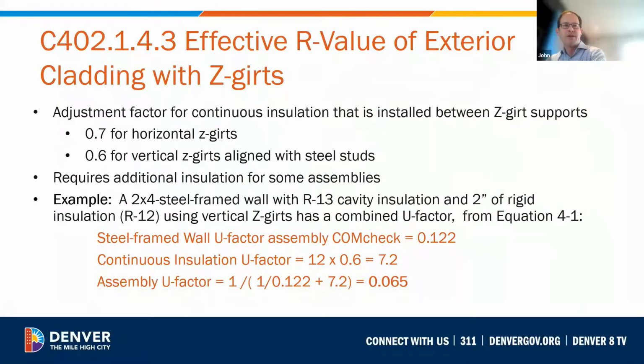So the simple example shows a steel frame wall with cavity insulation and 2 inches of rigid insulation using vertical girts. There's a simple equation for combining the effective R value of the exterior insulation with the Z-girts with the main cavity insulation. So the continuous insulation of R12 would be derated by a derating factor here of 0.6. So effectively, it would have an R value of R7.2. And then that would be used to determine the U factor for the assembly.